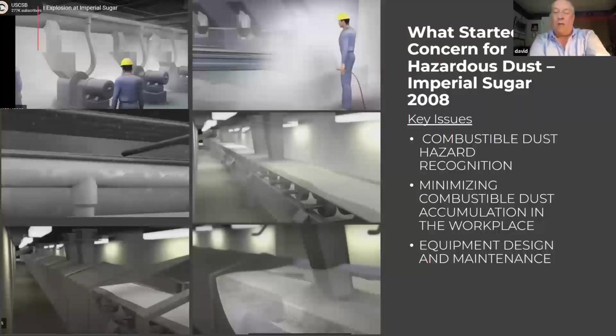So that worked well until you had a blockage on that conveyor line, which began to spill the sugar onto the floor and other surfaces. Even with ventilation in there, it was causing dust underneath all those covers. What happened? The dust spilled, it got onto the motors and hot bearings, which caused an ignition and explosion inside of all those covered areas on the conveyor. That then led to secondary explosions throughout the whole facility, because of all that dust up in the rafters and on other surfaces. It all got in the air and started igniting and exploding.